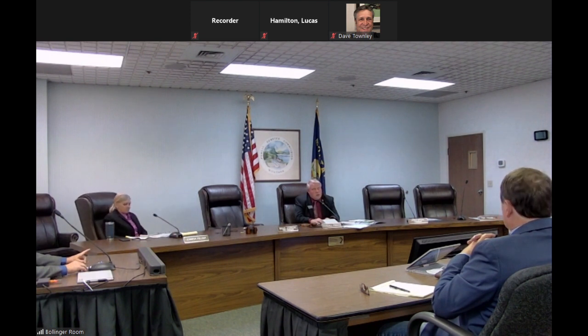Again, the numbers look really good, but a couple of individuals thought it was unrealistic because other power providers in the country couldn't have numbers that good. On our transmission system, those are the calculated losses we came up with in our rate filing, and we supported that at the Montana Commission and at FERC. We recover in our rates for losses based upon that, so if our losses were significantly greater, we'd be under-recovering our costs. We stand by those numbers, and I feel good about them, especially how they came down about 50% over an 18 or 19 year period, primarily because of the equipment we've taken out of service and replaced.